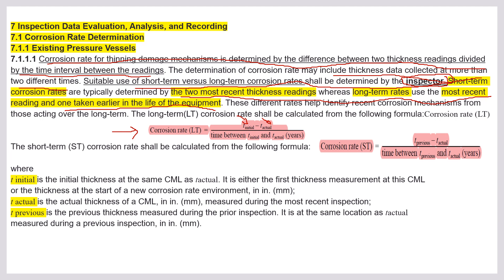In 2000 the thickness is 20 mm (t_initial = 20 mm) and t_actual is now 10 mm. The time between 2000 and 2022 is 22 years. So the long-term corrosion rate = (t_initial − t_actual) / years = (20 − 10) / 22 = 10/22. That result is the long-term corrosion rate.